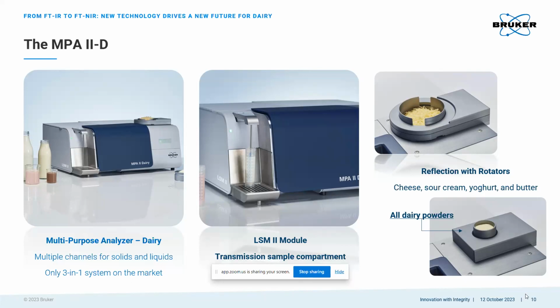And as we'll see shortly, the LSM module includes both a homogenizer as well as a peristaltic pump. And whether the liquid sample is homogenized on the way to the flow cell or simply pumped with the peristaltic pump is completely software controlled. So this way, the various types of liquids can be analyzed in transmission, regardless of viscosity or the content or size of particles. And what this combination provides is a complete solution for any type of sample in a dairy lab. So this is reducing the number of instruments needed, potentially down from 2 or 3 down to 1.